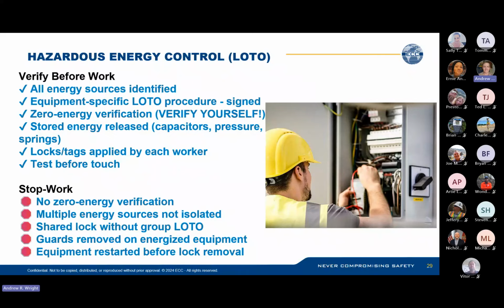Stored energy release: capacitors, pressure, springs, that sort of stuff. Locks and tags applied by each worker. So if you've got multiple trades, add a hasp on there and have multiple locks on there. And then your test before touch. So when will we stop work? No energy verification, multiple energy sources not isolated, a shared group lock, a shared lock without a LOTO, guards removed on energized equipment, and equipment restarted before the lock is removed.